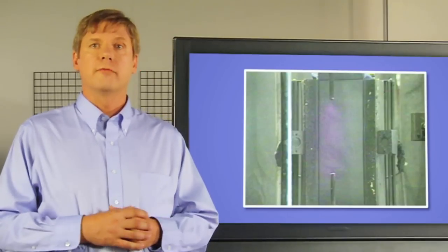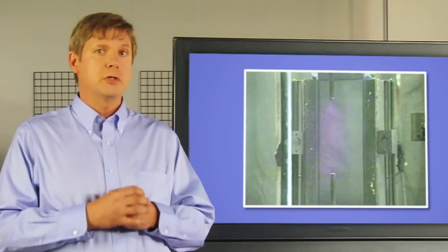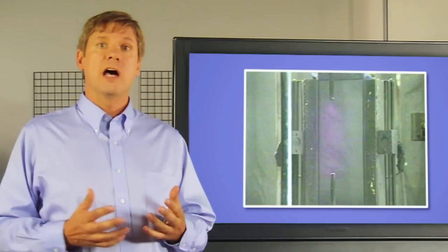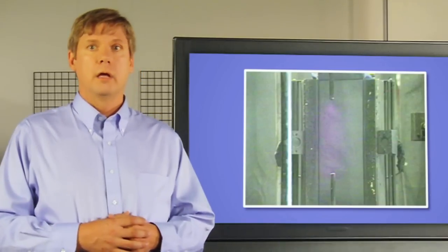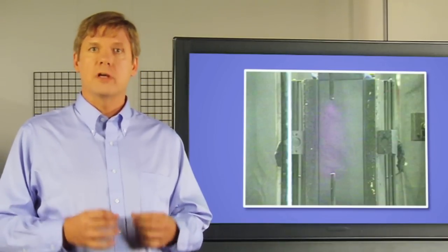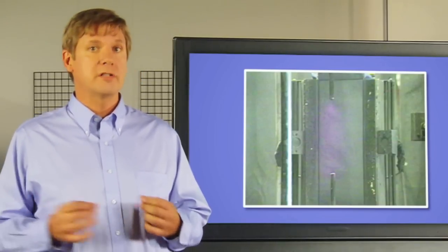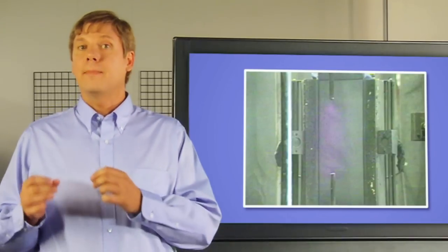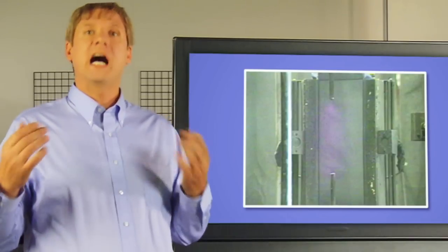It is important that the arc rating of your garment is above that of the potential arc flash exposure for any given work function. This is also how the industry standards have been written. So if your potential exposure is 7.5 calories per square centimeter, then your FR clothing needs an ATPV or EBT value equal to or higher than that.